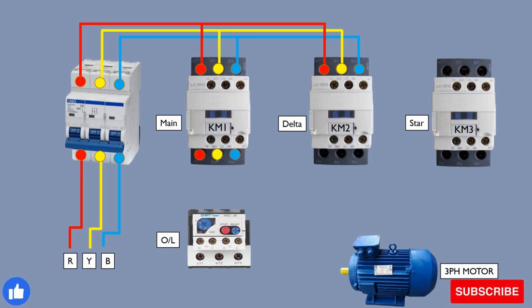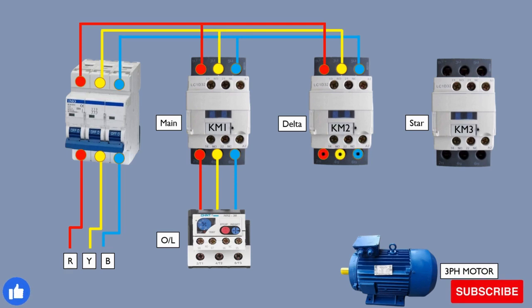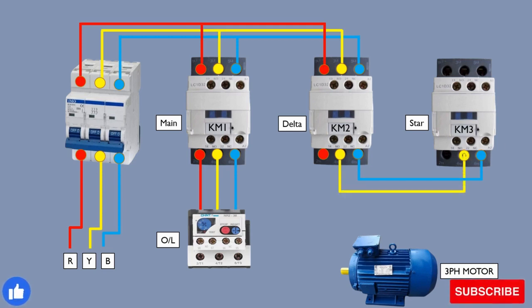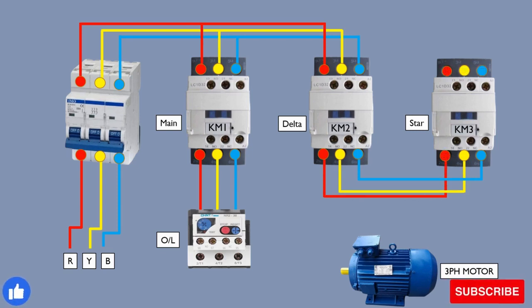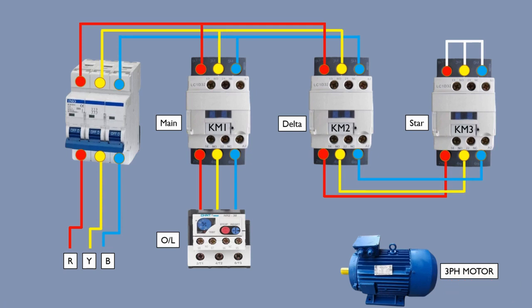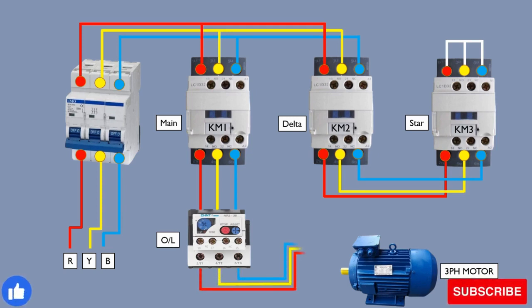From the output of the main contactor we make three connections to the overload relay, and also from the delta contactor to the star contactor from the output of the star. The other side of the star contactor will be looped to connect each other. Then we take the power from the overload relay to the motor, and also from the delta contactor to the motor.